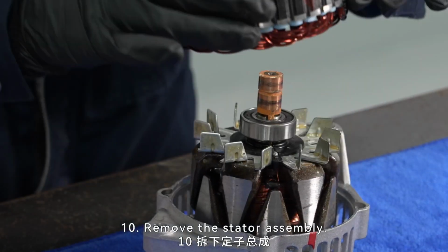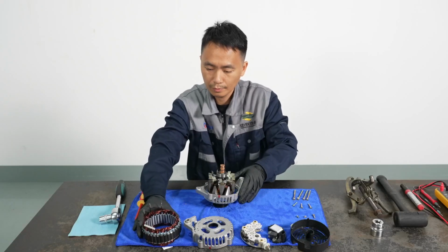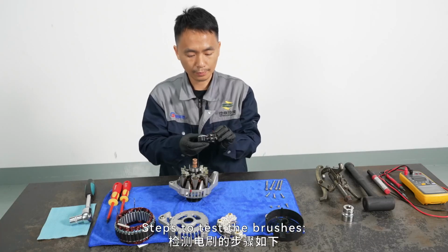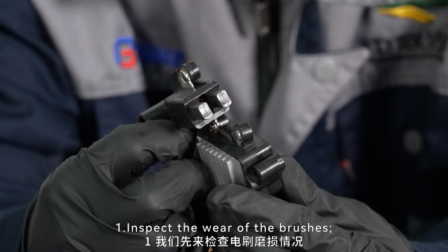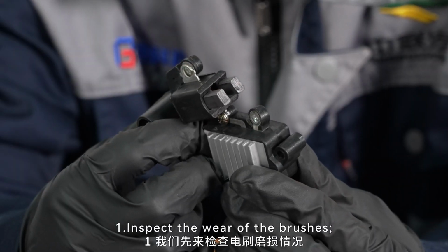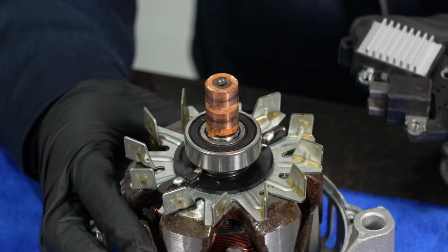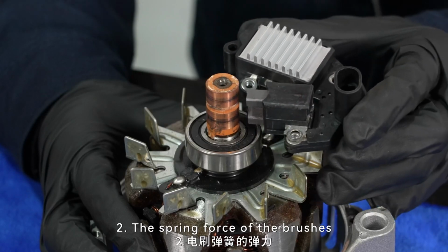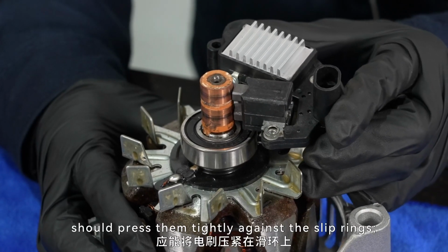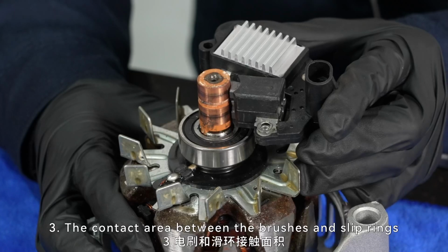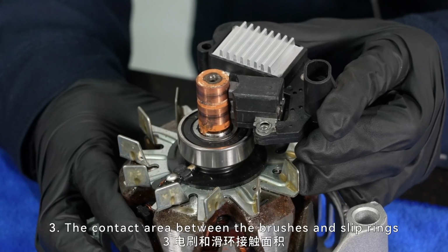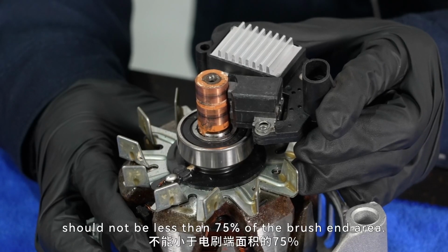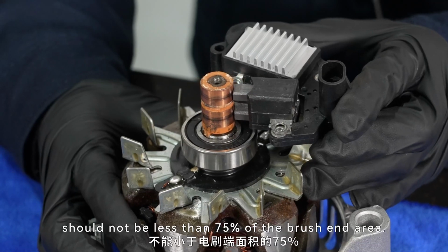Remove the stator assembly. Steps to test the brushes. 1. Inspect the wear of the brushes. 2. The spring force of the brushes should press them tightly against the slip rings. 3. The contact area between the brushes and slip rings should not be less than 75% of the brush end area.